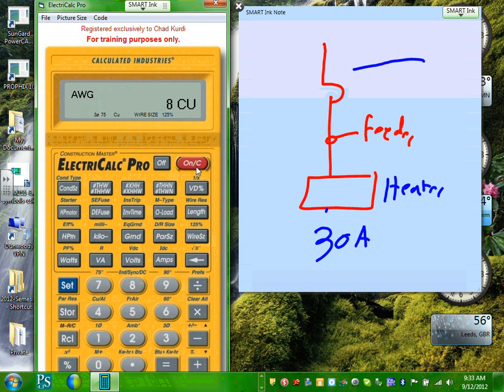All right, so again, clear it. Clear it. Let's go one more time. Let's say I have an HVAC machine, and the machine was pulling 120 amp. Can you guys put 120 amp? 120 and hit amps. Cool. 120 amp machine, three phase, and because continuous, I'm going to go set and wire size. So the size is 8 copper. Hit the first one. Here's how much kcmil that is. Hit again. Here's your kcmil.